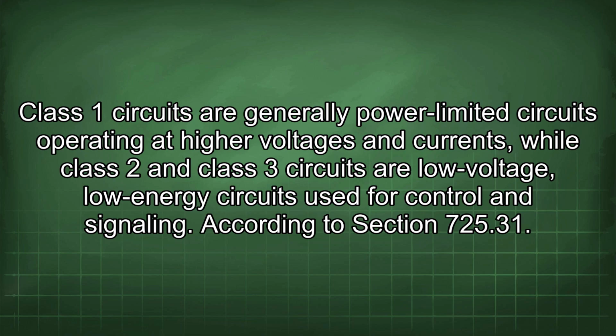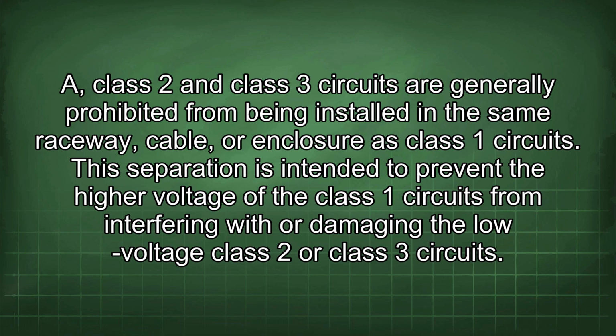According to Section 725.31, Class 2 and Class 3 circuits are generally prohibited from being installed in the same raceway, cable, or enclosure as Class 1 circuits. This separation is intended to prevent the higher voltage of the Class 1 circuits from interfering with or damaging the low-voltage Class 2 or Class 3 circuits.